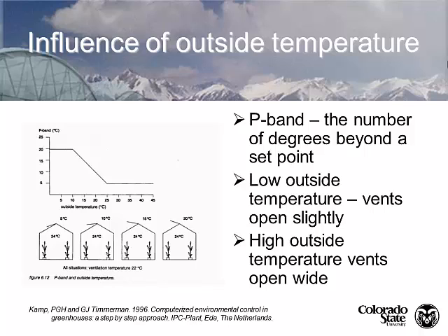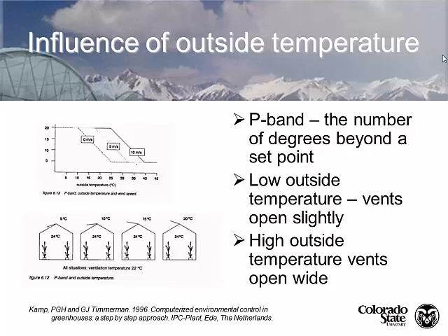The P-band will be based upon the temperature difference between the inside and outside temperature. If the P-band is wide, we're going to have the vents only open say 10%. As the P-band becomes lower — the difference between inside and outside becomes smaller, for instance 80°F versus 50°F, 60°F, or 70°F — you're going to open your vents at differential levels based upon that P-band. It's a more efficient way to run your greenhouse, and you can control these concepts in your climate control system.